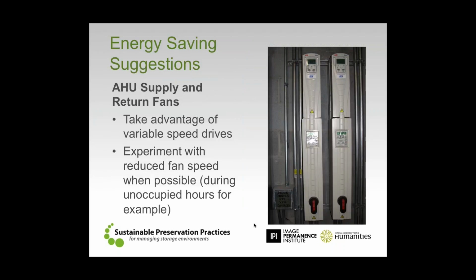Now, we're going to start getting into just some broad suggestions here, and how to think about what type of equipment I have, and how I might think about trying to reduce some energy use. The first step is just thinking about fan consumption and how fans use energy. There are a lot of institutions out there that have variable speed drives installed on supply or return air fans for mechanical systems, and a variable speed drive really is just a dimmer switch for a fan motor. As you increase the speed of the fan, it moves faster and circulates more air.